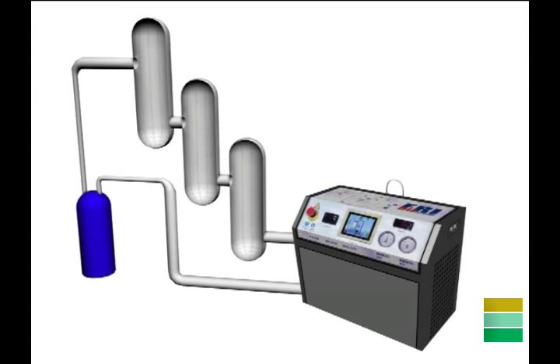Where the required quantity of refrigerant is greater than the 60 kilos of the refrigerant bottle, it will be necessary to divide the circuit to be cleaned into smaller sections. However, it is useful to know that a 60 kilo bottle is enough to clean a system up to 50 horsepower. An extra refrigerant bottle can be used if we notice that the amount is not enough once the process has been initiated.